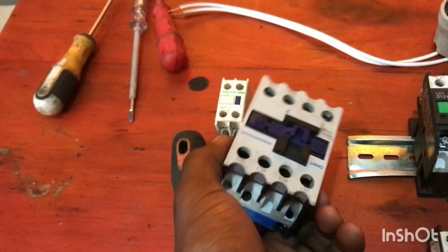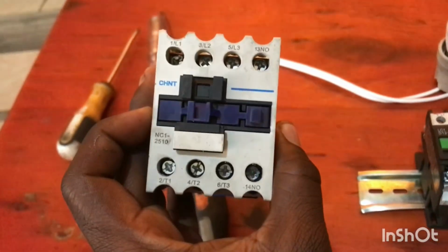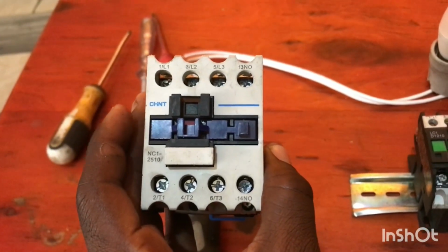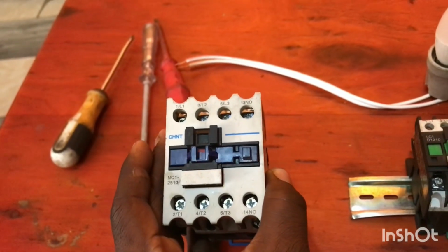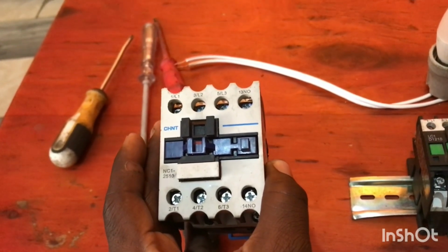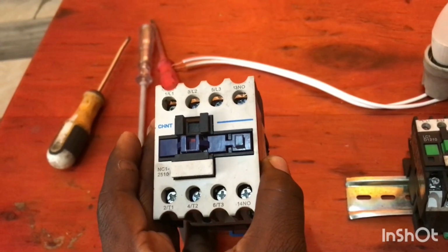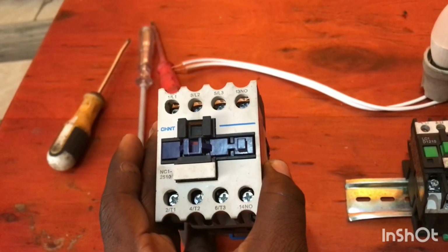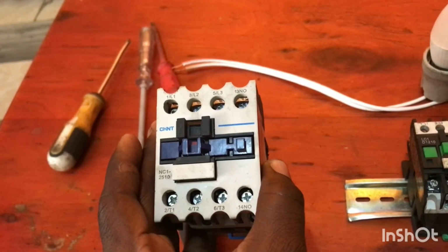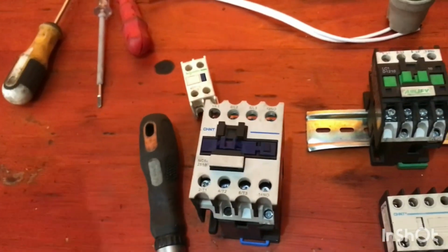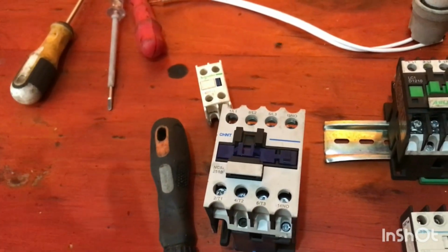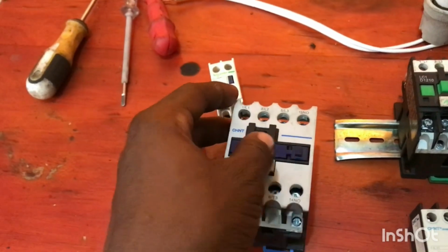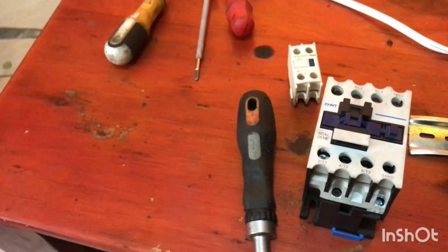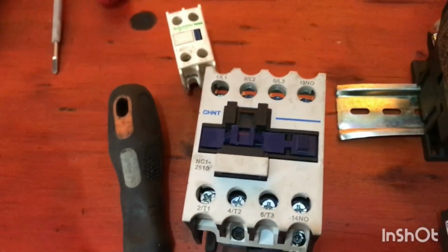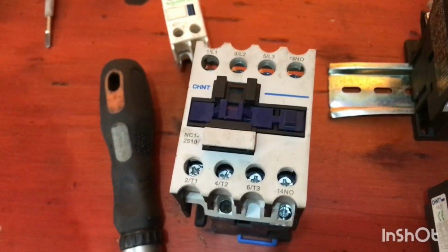So inside this contactor there are some electromagnetic relays. These relays are the ones which, when they get energized, make contacts between point A and point B. So on this contactor that I'm holding, these parts that you see marked L1, L2, L3 and normally open are the contacts where electricity or current is transferred from point A to point B, or where contacts are being made automatically.